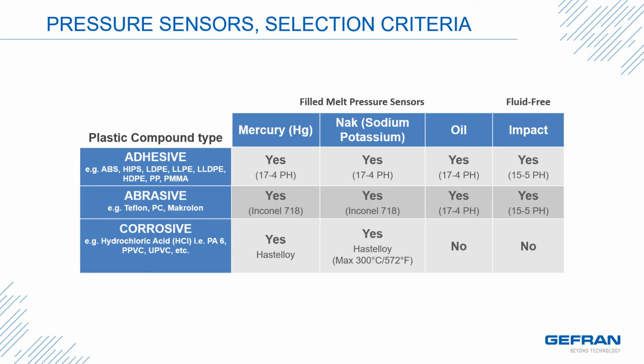Choosing which sensing technology would be best for your application is not always a 100% exact science, but based on the plastic being processed, the compound type, we can break down these qualities into 3 groups. The plastic compound will either exhibit adhesive properties, abrasive properties, or corrosive properties. And yes, it's also possible for there to be some combination of those, but usually one is more prominent than the others. So based on this, we've produced this little chart just to give an idea of what the best possible choices are in terms of the sensing technologies based on the plastic compound being processed.